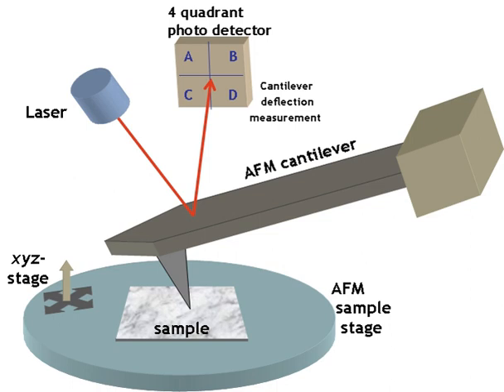SECM utilizes many of the same positioning components available to other materials characterization techniques. Precise positioning between the tip and sample is an important factor that is complementary to tip size. The position of the probe relative to a given point on the material surface in the X, Y, and Z directions is typically controlled by a motor for rough positioning coupled with a piezoelectric motor for finer control. Systems may feature an inchworm motor for coarse positioning with additional Z control governed by a PZT piezo pusher, or stepper motors with XYZ piezo block positioner or closed-loop controller systems.